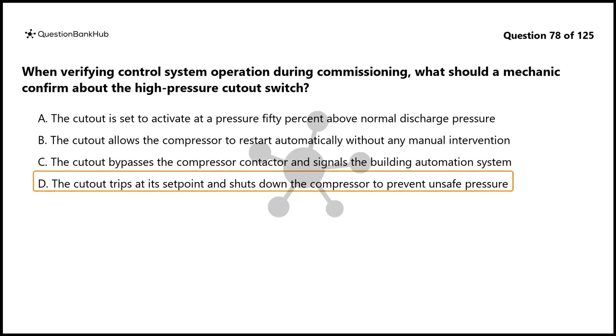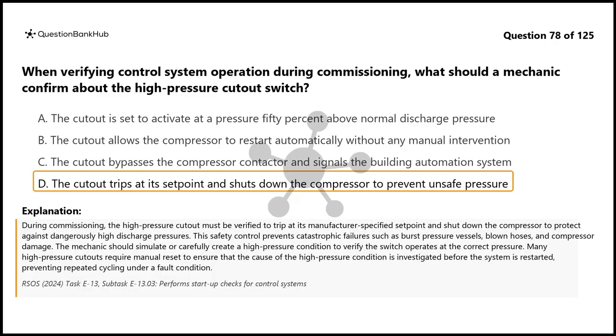The correct answer is D. During commissioning, the high-pressure cutout must be verified to trip at its manufacturer-specified setpoint and shut down the compressor to protect against dangerously high discharge pressures. This safety control prevents catastrophic failures such as burst pressure vessels, blown hoses, and compressor damage. The mechanic should simulate or carefully create a high-pressure condition to verify the switch operates at the correct pressure. Many high-pressure cutouts require manual reset to ensure that the cause of the high-pressure condition is investigated before the system is restarted, preventing repeated cycling under a fault condition.